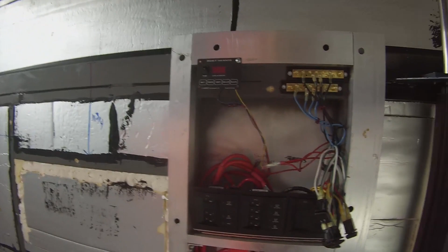And that seems like a lot for 12 volt DC, but each of the actuators had to have a 40 amp breaker. They really only pulled 20 amps, but they have like a 40 amp draw for 250 milliseconds, so they need a 40 amp breaker, otherwise you'll get nuisance tripping.